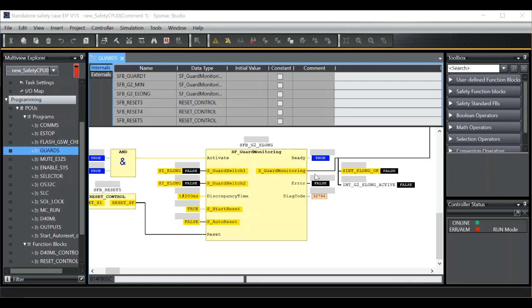IO cannot be forced on verified programs. It's important to remember that forcing safety IO even in the commissioning phase can lead to hazardous situations. Temporary guarding or policies may need to be applied to allow this function to be safely used. A full risk assessment should be carried out before progressing.